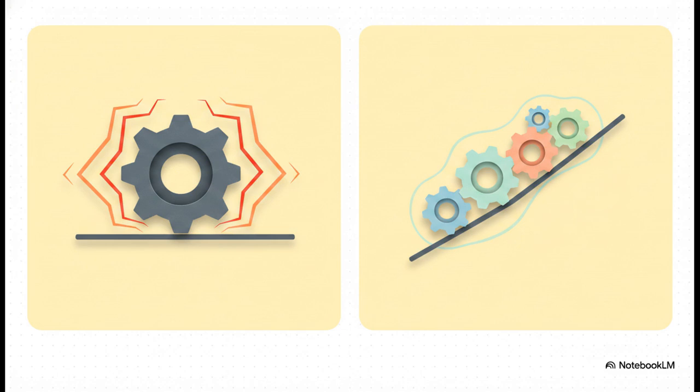It lets the engine speed drop slightly as the load increases. By not fighting to return to the exact starting speed, the governor doesn't constantly overcorrect. And even better, it allows multiple generators on a grid to independently vote on the system frequency. If the load increases, they all just naturally slow down a little bit together, sharing the burden proportionally without ever needing to communicate with each other. It's a real game changer.